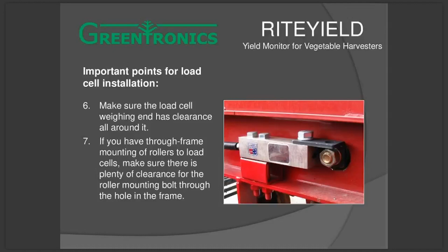The load cell needs to have clearance, so you shouldn't mount it so that it's tight against the frame. It needs to be free from the frame, especially the weighing end of the load cell. And in this picture here, you see how the roller is on the inside of the frame, of course, underneath the belt, and it's mounted to the load cell on the outside. So you need good clearance around where that bolt goes through the frame. So if that bolt touches the frame, then the load cell doesn't see exactly what the weight is on top of the belt. That makes sense. And it's not hard to do, just something to keep in mind.